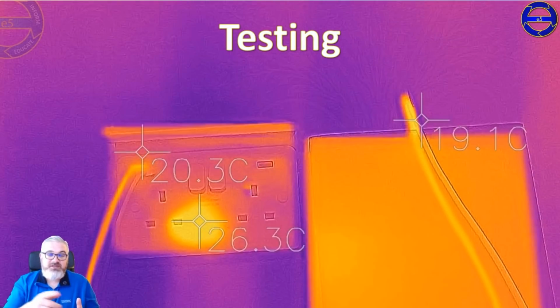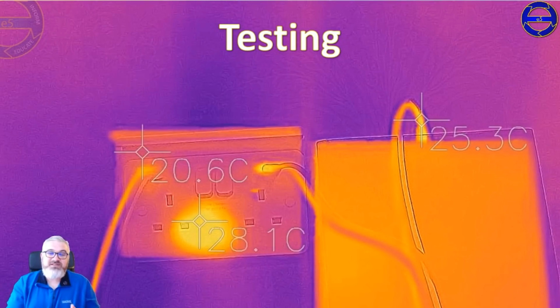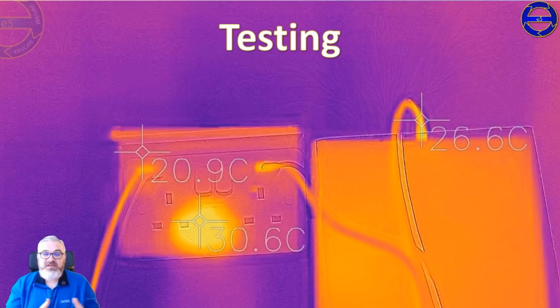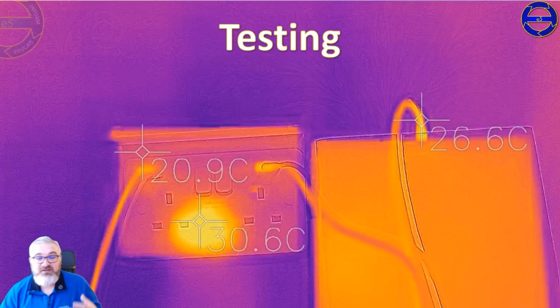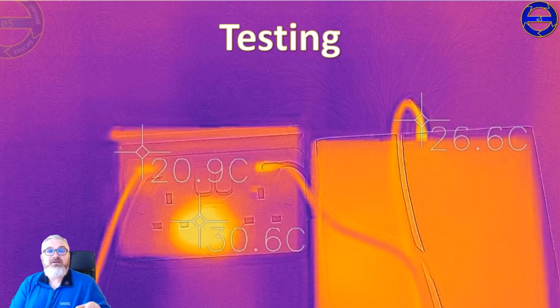As you can see, the wire is getting warm from carrying the current. I've then plugged a second device in, and what you can see straight away from the faceplate is there's a 10 degrees difference and a 4 degrees difference at the point of delivery. So it's a fascinating view of how these devices perform under thermal stresses. Now thermal stresses are really important because they're an external influence, but a USB charger now introduces an external influence within the fixed body of a socket. So getting the quality right for a socket outlet with a USB is really important to the safety of the installation, in my opinion. And I'm sure if you have different opinions, you'll put them in the comments below. But again, it's a fascinating insight.